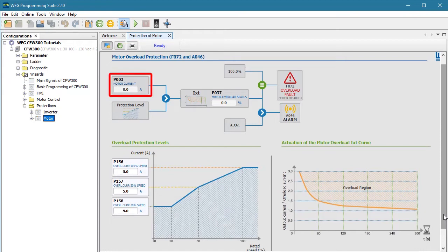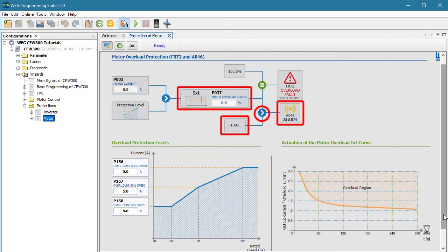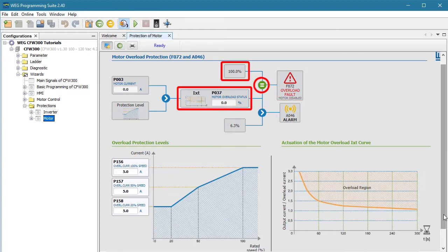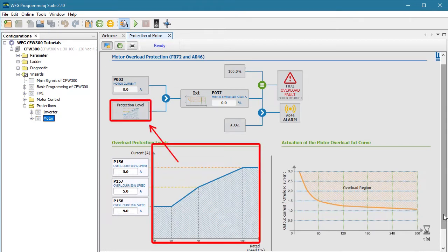It says if the motor current is greater than the allowed protection levels, which are defined down here, and it does it for a certain amount of time, which the drive converts to percent overload — if that overload percent rises above 6.3% then it issues an alarm, and if it hits 100% it issues a fault which shuts down the drive's output. Using these three parameters, you can customize the overload curve however you want.